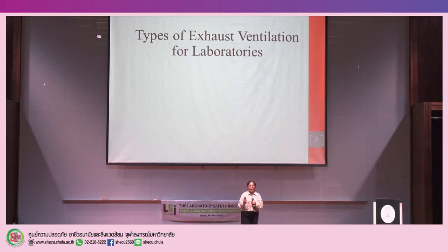A lot of people, when asked, do you have ventilation in your lab? Yes, I have it. I have an air conditioner. An air conditioner is not a ventilator. It doesn't take any of the toxic chemicals out. It just recirculates. And the chemical bottle is sitting in your room and it generates toxic vapor every day. And it doesn't go anywhere. It just leaks out when you open the door and go in and out, that's it.